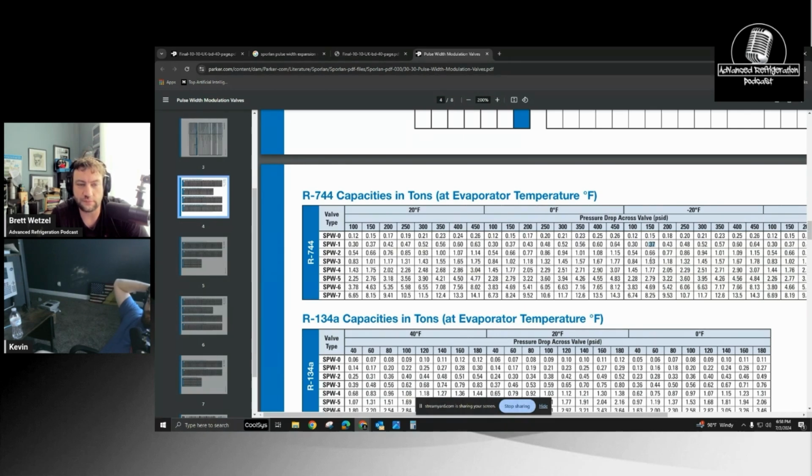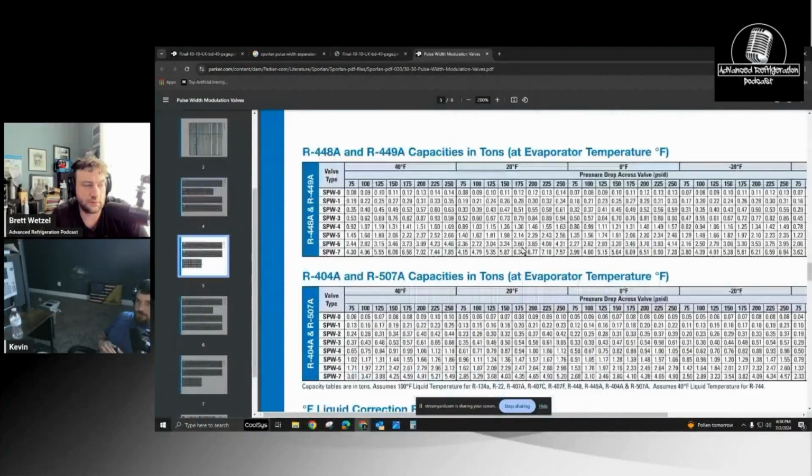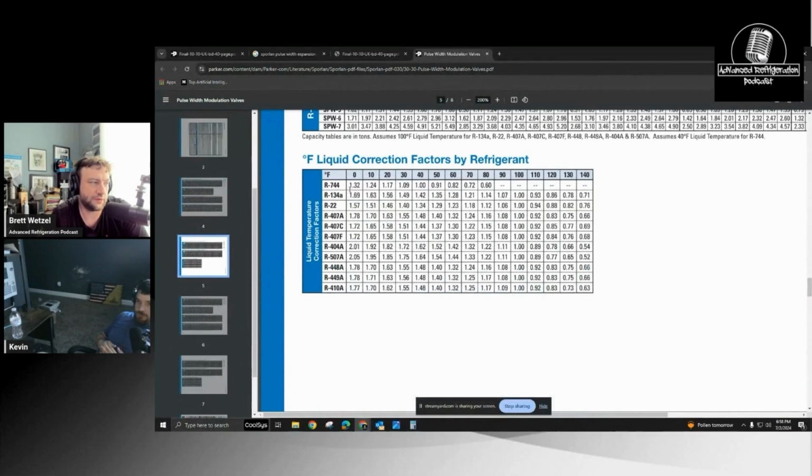Yeah, but I saw a rack the other day with one. Really? It was piped to a single unit, and it was subcooling. What was the set point? The flash tank was saturated at 33, and it was bringing the liquid down to 25. Really? Yep. A little tiny 3-phase scroll unit. So they actually do have it.